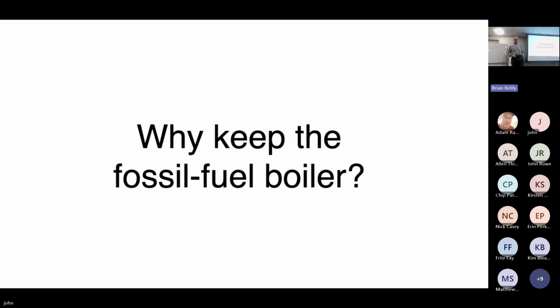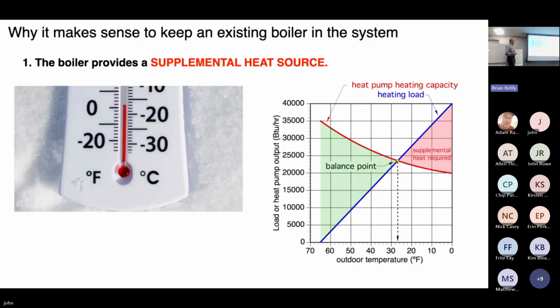All right. So I put a segment together here, and again, we have clientele that would choose to eliminate all fossil fuels from a project. I understand it. I get it. We also have clientele that would say, well, if I have a boiler in the system and I'm going to add a heat pump, should I or can I keep the existing boiler as both supplemental heat and backup heat? So I'm going to try to make the case for why I feel that there are definitely some benefits to keeping that existing boiler in place.